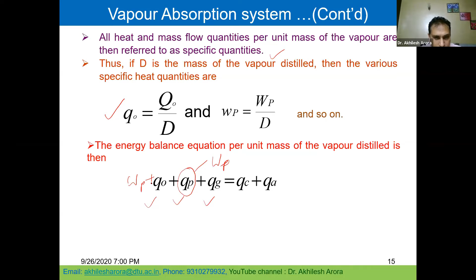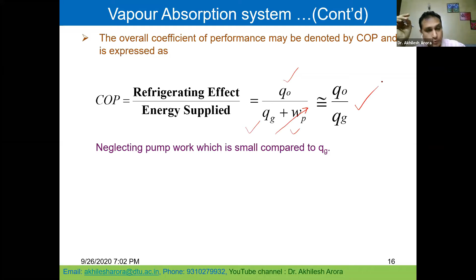COP is refrigerating effect divided by the energy supplied. So what is the refrigerating effect? It is the cooling effect produced in the evaporator divided by the energy which we are inputting into the system for operating the system, and that energy is the heat which we are supplying in the generator and the pump work. These are the two things that we are supplying. But as I told you, the pump work is very small, so we can always neglect this particular value, and then the COP is approximately equal to Q naught divided by QG. It will not vary much by considering the pump work to be negligible, because it's very small.